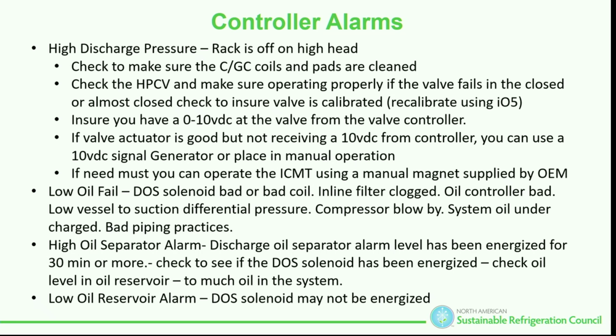All right, high separator alarms. Discharge oil separator alarm has been energized for 30 minutes. The sensor on the bottom of the separator has been energized for 30 minutes. Does that sound like a problem? If my separator is holding oil for 30 minutes, is that a problem? What would be the easiest thing it could be? There's a solenoid that goes between the separator and the reservoir. A lot of times that high separator alarm will be followed by a low reservoir alarm.